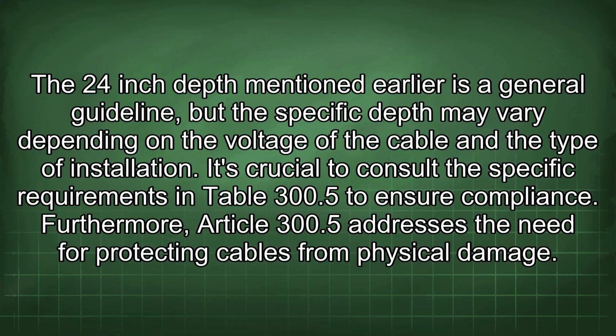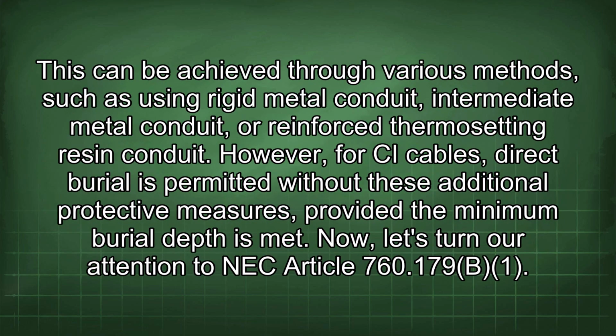Furthermore, Article 300.5 addresses the need for protecting cables from physical damage. This can be achieved through various methods, such as using rigid metal conduit, intermediate metal conduit, or reinforced thermosetting resin conduit. However, for CI cables, direct burial is permitted without these additional protective measures, provided the minimum burial depth is met.